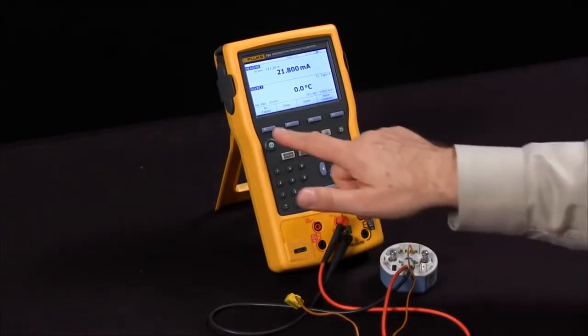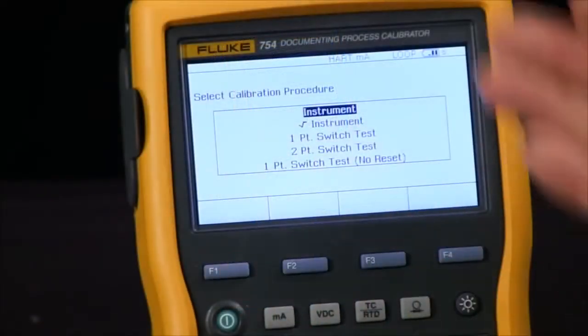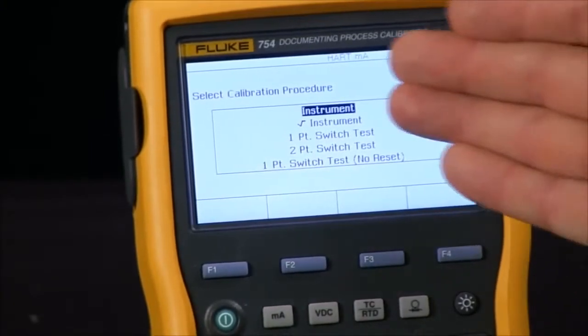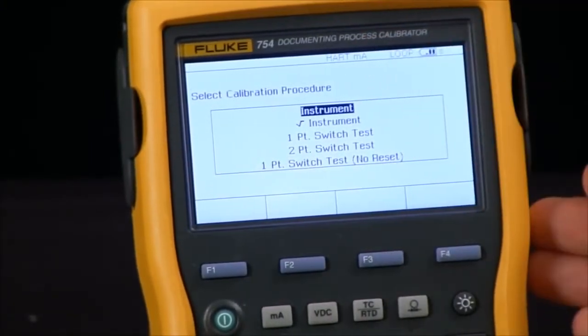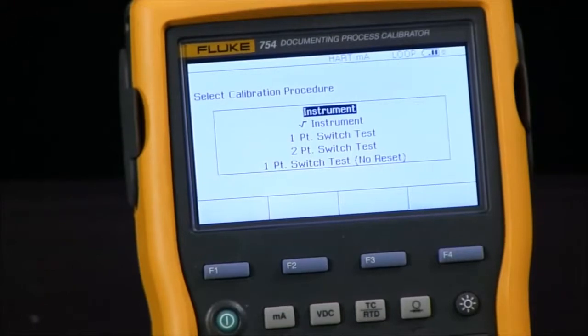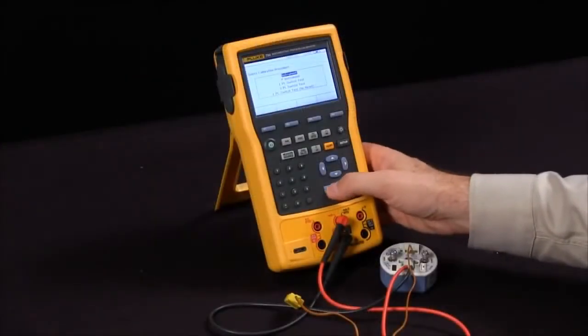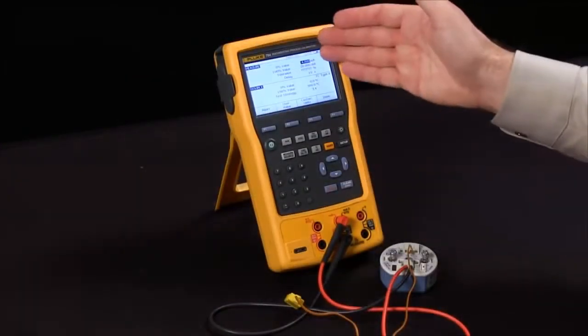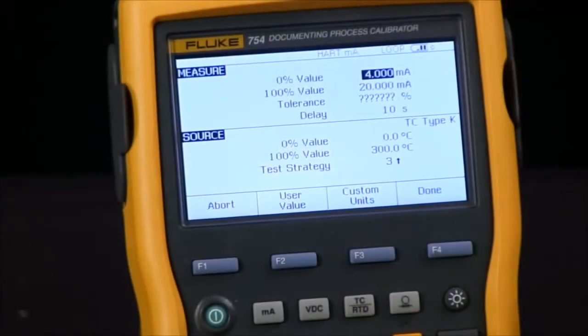We will do an as found. And now what do I want it to do? I can do an instrument. If I were doing flow, I can do square root instrument. But since we're just focusing on the temperature calibration, I will select instrument. Right now, my upper and lower range, I'm going from a 4 to 20 milliamp.